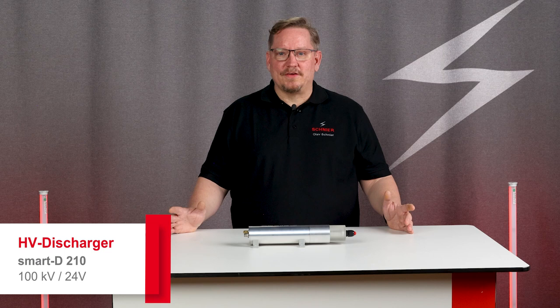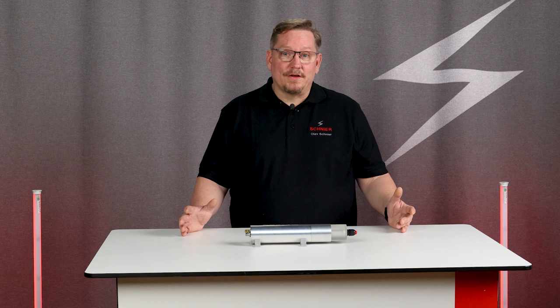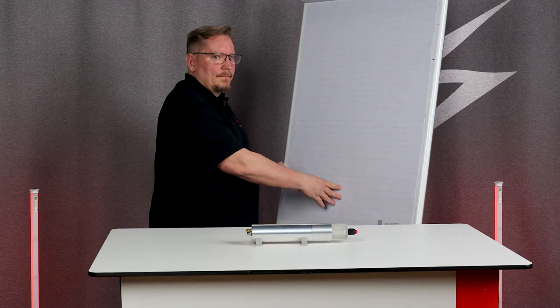So, when should I use it? Quite simply, whenever time plays a role. That is, when I want to be discharged as quickly as possible after switching off the high voltage. Normally, high-voltage systems are discharged purely via the measuring resistor of the high-voltage generator. The discharger is extremely fast, but let's take a quick look at this in detail.